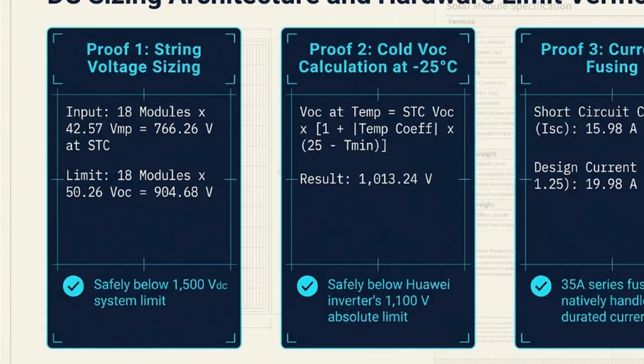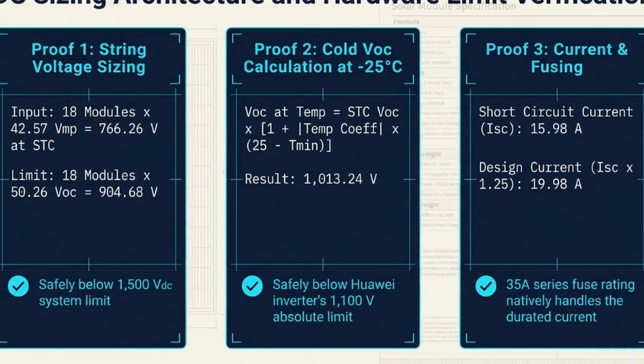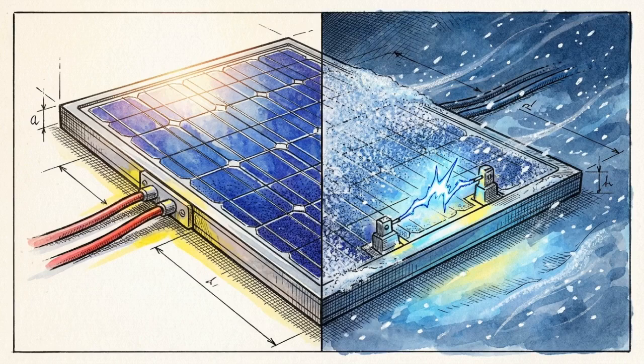We can see the string voltage sizing proofs here. Under standard test conditions, wiring 18 modules yields 904 volts. Adjusting the calculation for a minus 25 degrees Celsius threshold pushes the voltage to 1,013 volts, safely below the inverter's absolute 1,100 volt limit. Direct current system design requires mathematically proving hardware survivability under the most extreme meteorological edges, rather than just planning for sunny days.